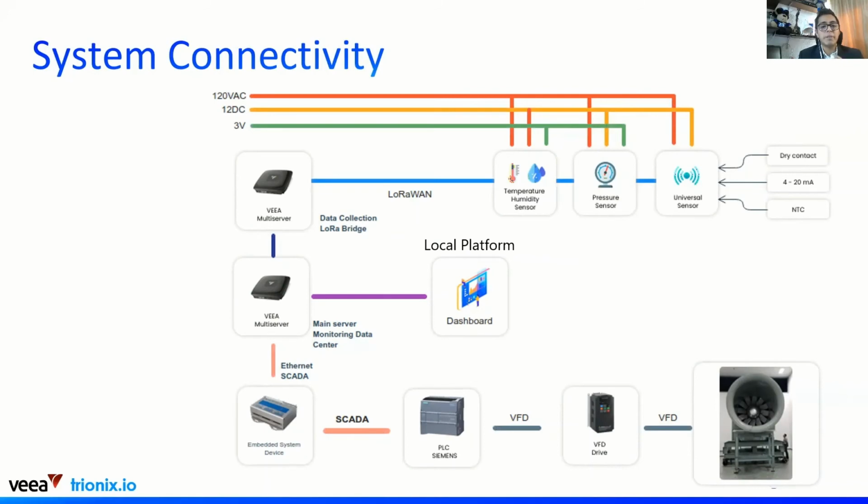The VeeaHub in the middle is the main server, which is in charge of getting the information from the sensing part, analyzing it, and determining what needs to be done with each one of the extractors and fans, setting this final state to the corresponding control equipment. Just as Mohan said at the beginning, the complexity of this decision-making is based on three main things. First, meteorological information. Second, the internal conditions of the tunnels and the current state of the equipment, in order to determine what needs to be done: a pollution extraction, a temperature regulation, or going to an emergency state.